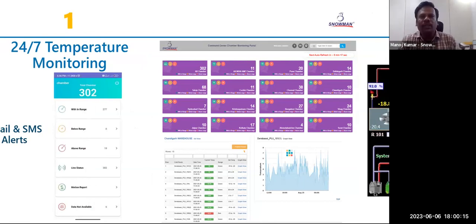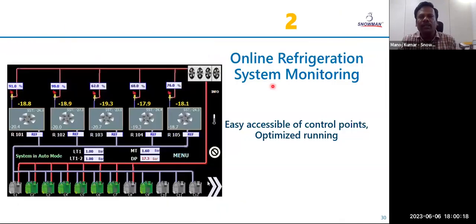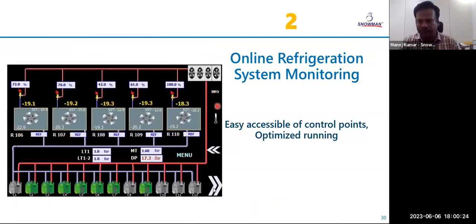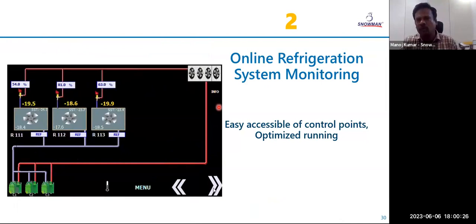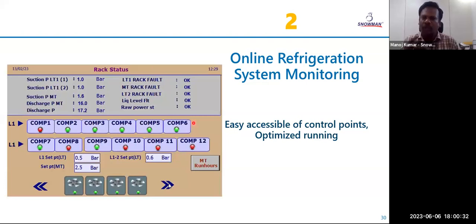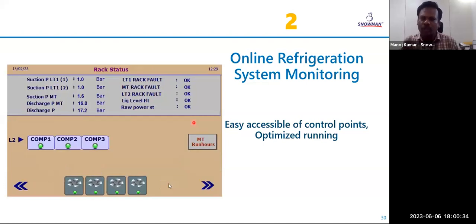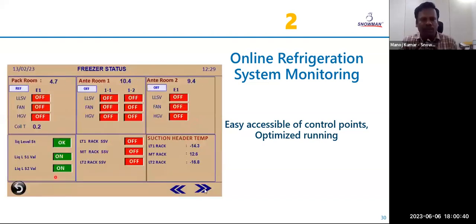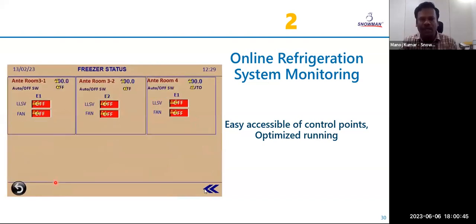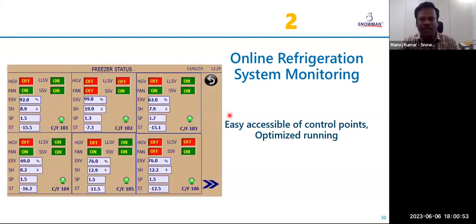Similarly, at our head office in Bangalore, we monitor all refrigeration parameters - for example, defrost parameters, fans running, compressors running, suction pressure, discharge pressure. We monitor all of this online across all 43 warehouses. In case of any issues, I'm able to get the information, and therefore we are able to maintain 135,000 metric ton capacity without any problem.